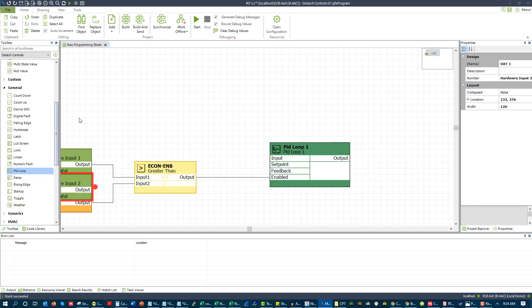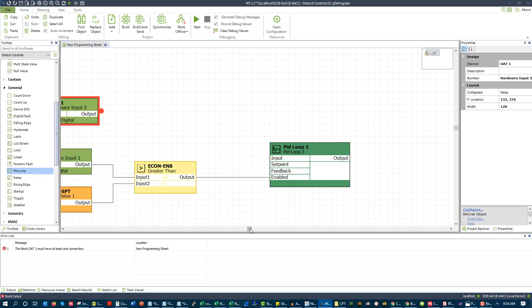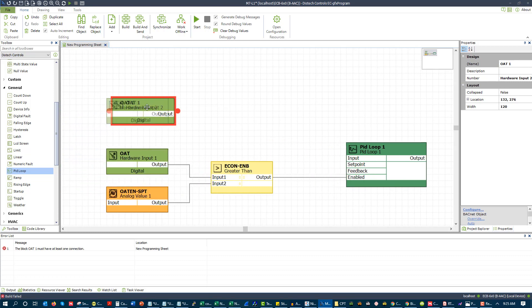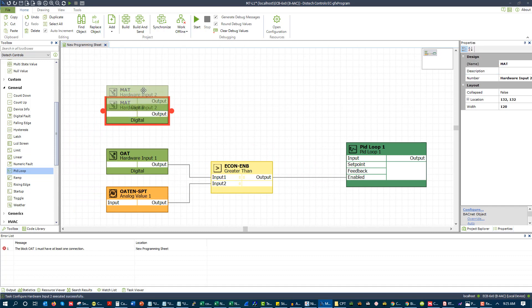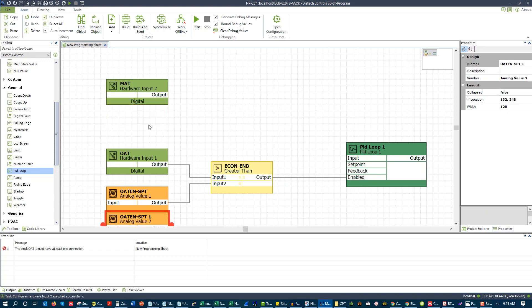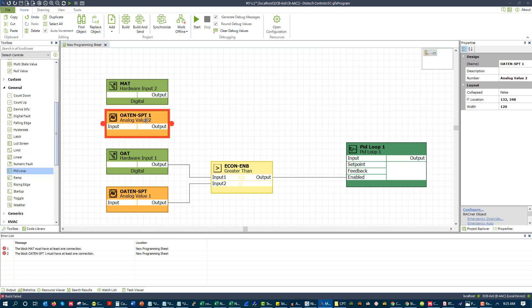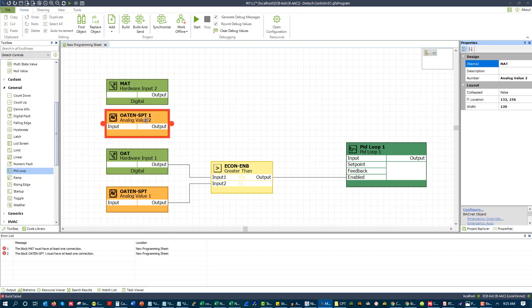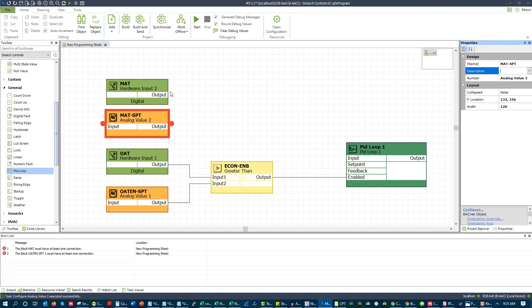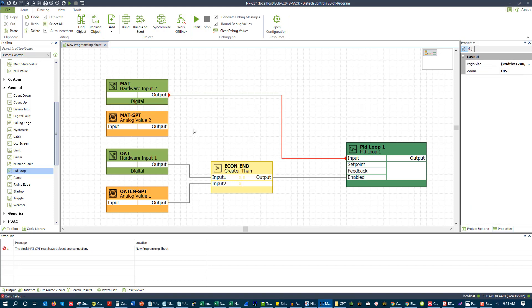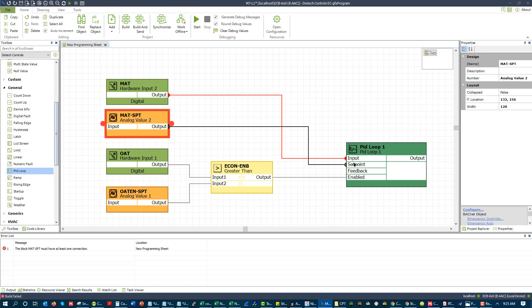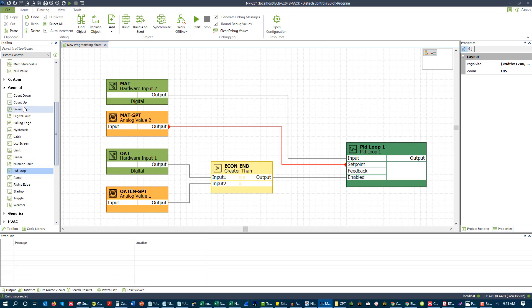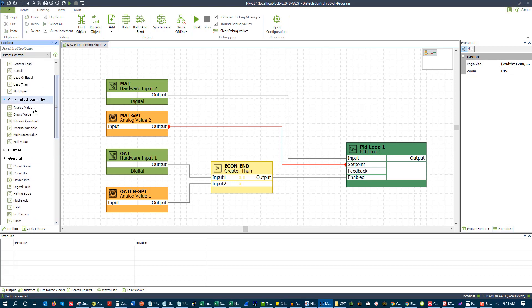Now this could then go and drive a PID loop that is driving towards mixed air temp. So let's grab another input and put this input up here. Let me drag this over a little bit so you can see it. We're going to call this input MAT. And let's create another analog value up here — we're going to call this MAT set point.